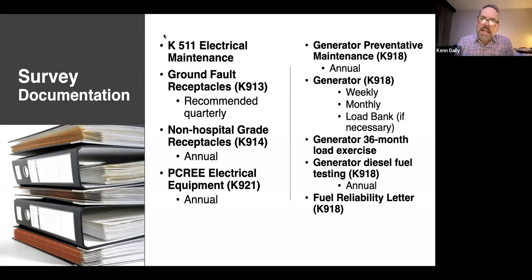And then you have PCREE, which is personal care related electrical equipment, and it needs to be tested on an annual basis. Well, that's things like your electric bed, the nurse on a stick, with your pulse ox, your temperature, that thing on a pole. Anything electric that's used for care on and around a resident requires testing once a year for things like line leakage and touch current and that kind of thing.